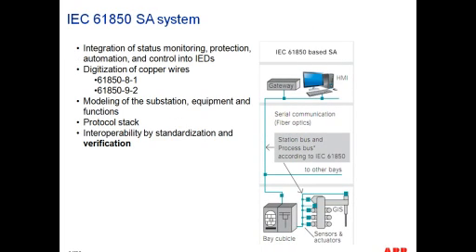And in essence, that's what IEC 61850 accomplished from a substation automation perspective and from a client-server perspective, which is essentially the relays sending information over to a master station or a gateway that will present all of this process-related information in a manner that can be consumed in an HMI or a mimic, so that the operator of the substation can get a good understanding of the status of the system. In addition to this, which in 61850 is called client-server, we introduced two different protocols. As part of IEC 61850-8-1, we have GOOSE messages, and as part of 61850-9-2, we have sampled measured values.